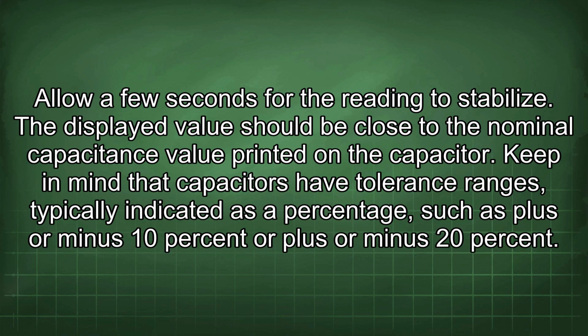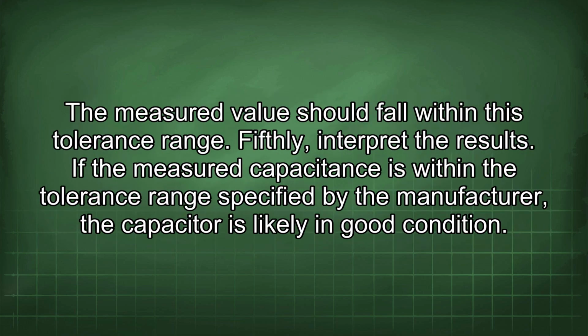The display value should be close to the nominal capacitance value printed on the capacitor. Keep in mind that capacitors have tolerance ranges, typically indicated as a percentage, such as plus or minus 10% or plus or minus 20%. The measured value should fall within this tolerance range.